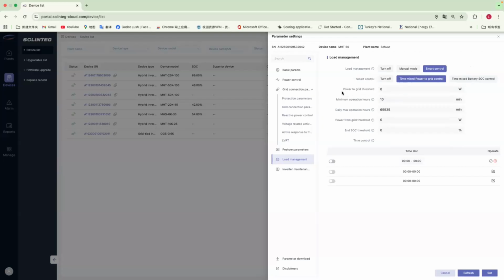In case the smart device turns on and off too frequently, we've set a minimum operation time. For example, if the actual power to the grid just exceeds the value set here, the smart device will run for at least 10 minutes. After that, if the actual power is lower than this set value, the smart device won't be able to work. We can also set the daily maximum operation hours, which is the longest time the smart device can run in this system.